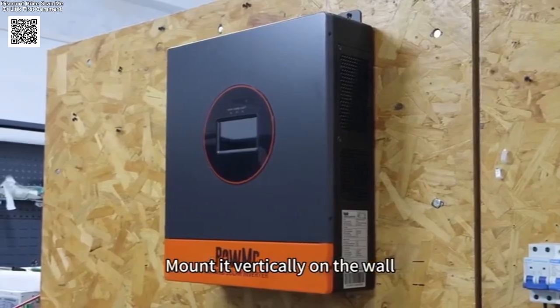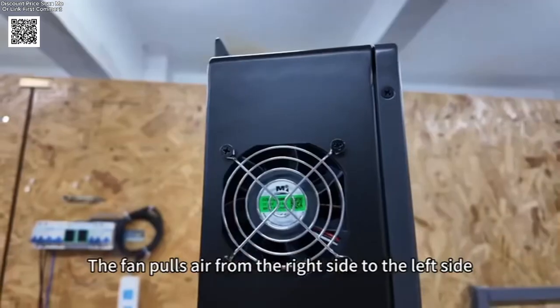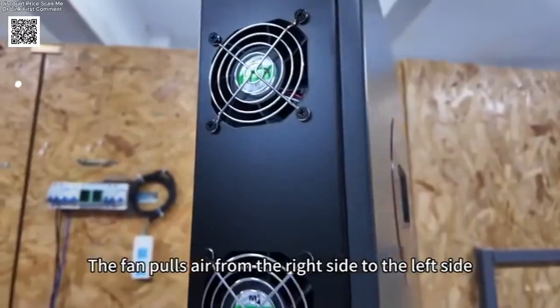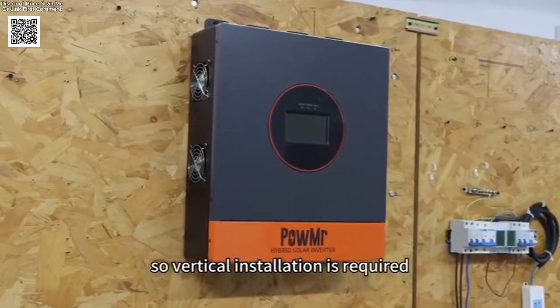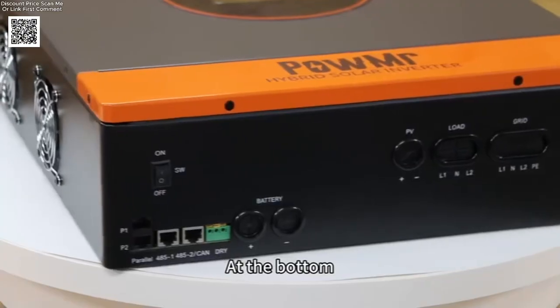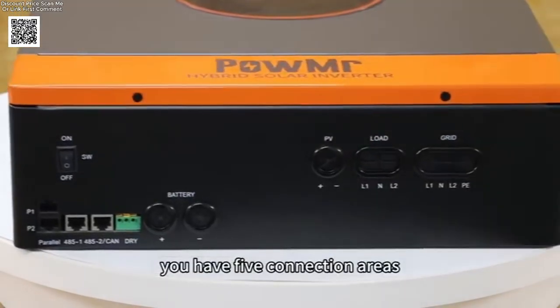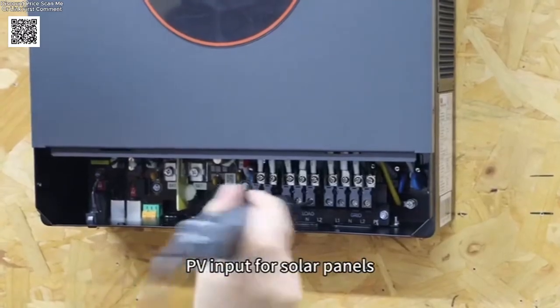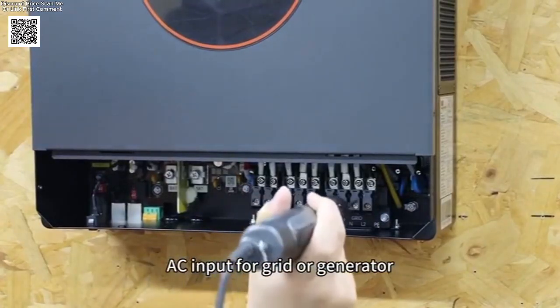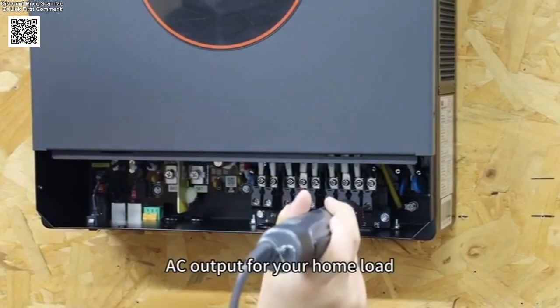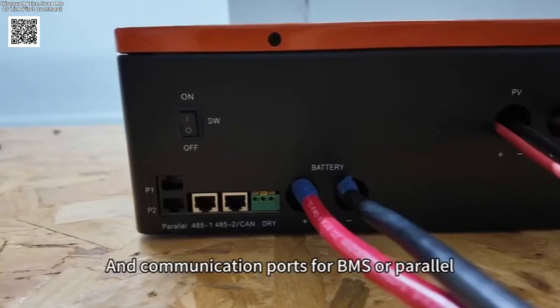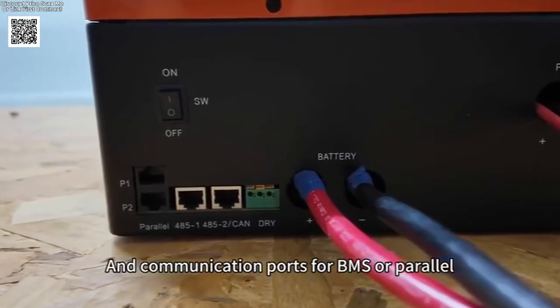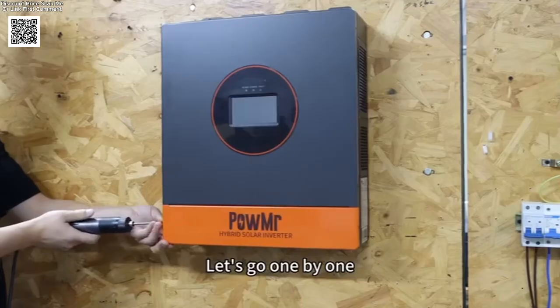Mounted vertically on the wall, the fan pulls air from the right side to the left side, so vertical installation is required. At the bottom, you have 5 connection areas: PV input for solar panels, battery for energy storage, AC input for grid or generator, AC output for home load, and communication ports for BMS or parallel. Let's go one by one.